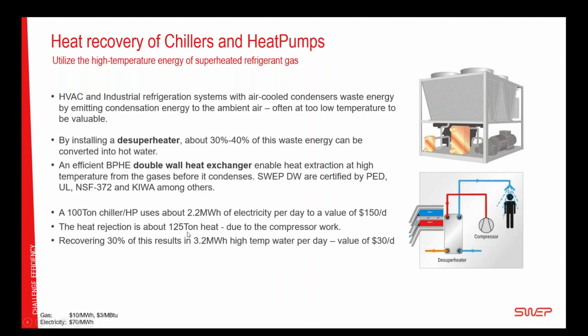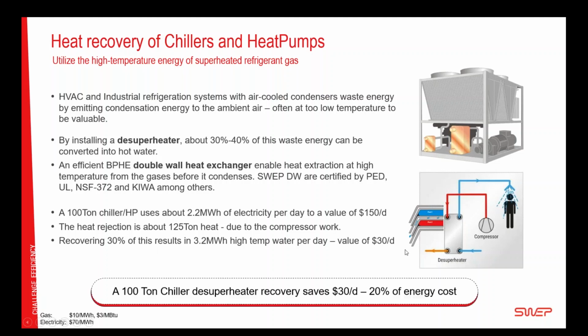Most of this is at the low temperature without so much value. But with the desuperheater, we can get let's say 30% of that energy at high temperature, which means 3.2 megawatt hour, and we have $30 per day in value there, and that's 20% of the energy cost. And even if you think, okay, $30, that's not so much money, but it's 20% of the energy that you put in there. And if you think of the factory working and you start to sum up all the different savings you have, there is a bottom line advantage that cannot be neglected.